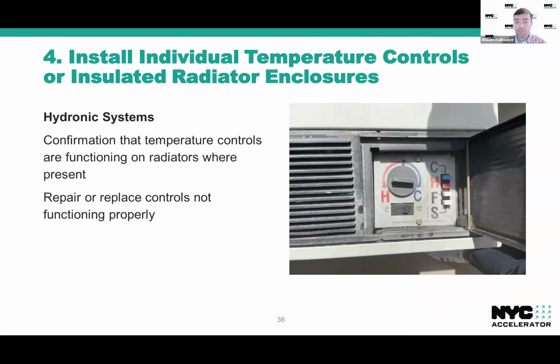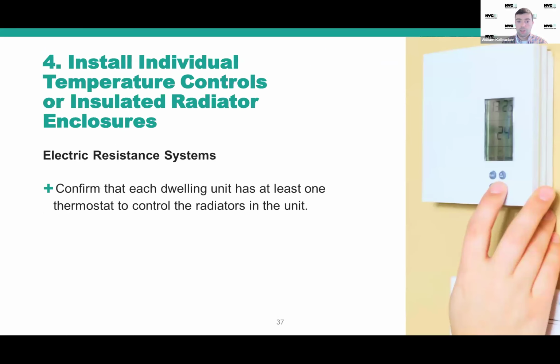On the hydronic side, you do want to confirm that there are functioning local controls at each heater that are not overheating the space. And for any units that are found to be broken, they need to be repaired or replaced. Similar for electric resistance systems, you want to ensure that there is at least 1 thermostat to control the radiators in each unit, and that it's working properly.